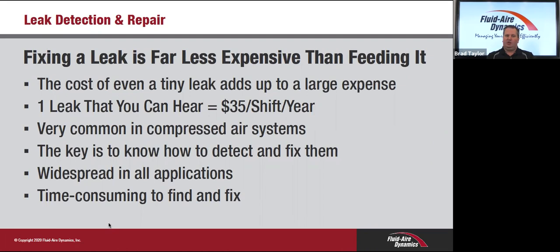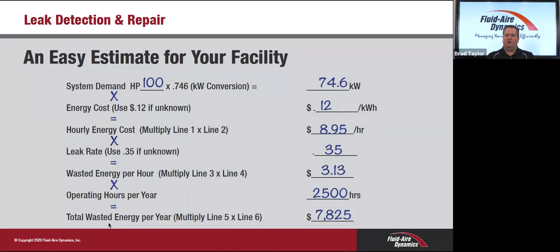There are some real easy ways to quantify those leaks, such as at lunchtime, break time, or end of day, see what the duty cycle is of your compressor when nothing's running. Then multiply that percentage by the output of your compressor, and multiply that by 35 if you're a single shift operation, or by 35 times 2 if you're a 2-shift operation. Or you could take the formula that Mike has up on the screen: plug in the kW of your compressor, or your horsepower times .746 to get kW, your energy cost including the associated taxes, and then multiply it down through the leak rate of 35% and the hours you operate, to come up with your energy cost.